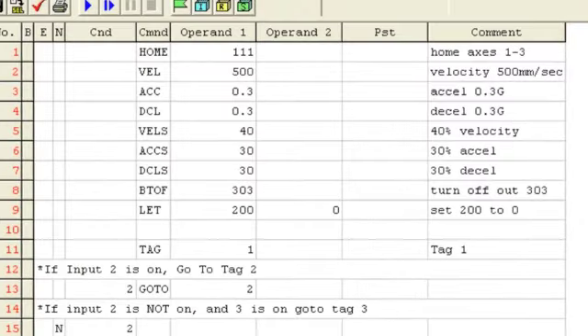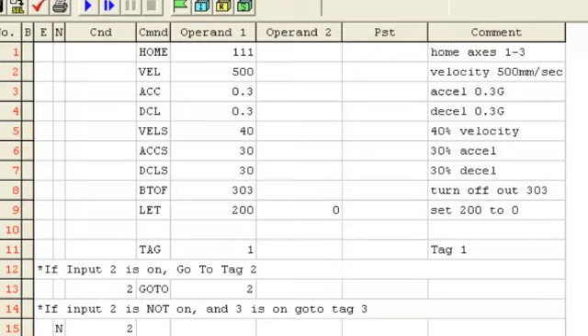Looking at this simple program: at the beginning, home all single axes that are not absolute type using the HOME command with an axis pattern in operand 1. After all axes are homed, set the program speed with VEL in millimeters per second and ACC and DCL in G. Once the velocity is set, you can initialize all variables and turn off all flags and outputs used inside the program. On line 8, output 303 is turned off. On line 9, variable 200 is initialized to a value of 0.